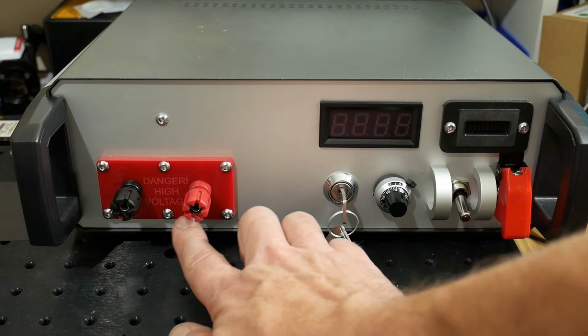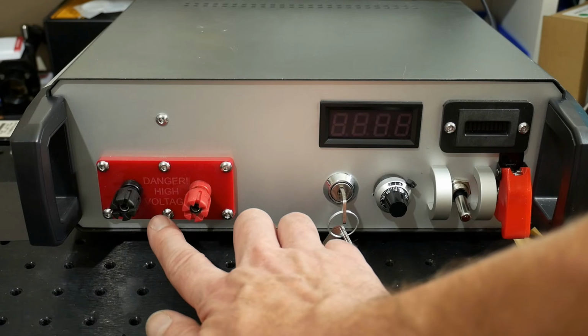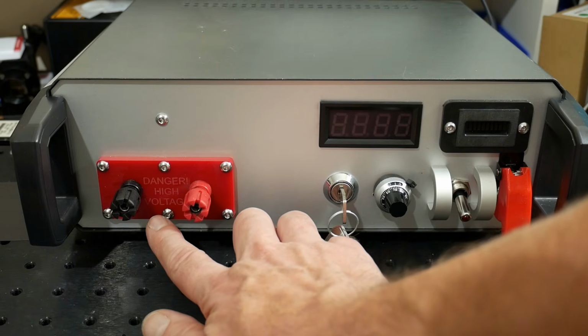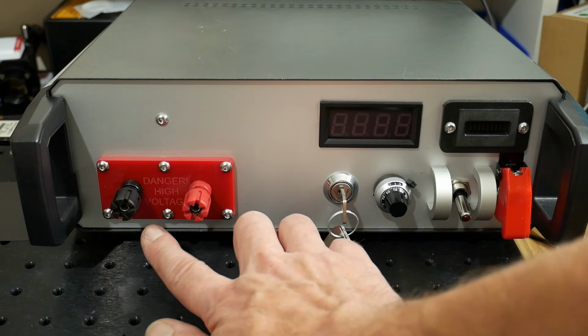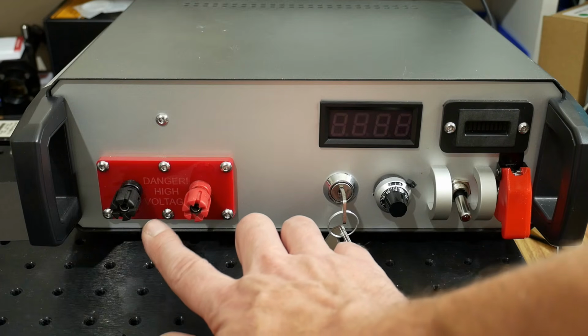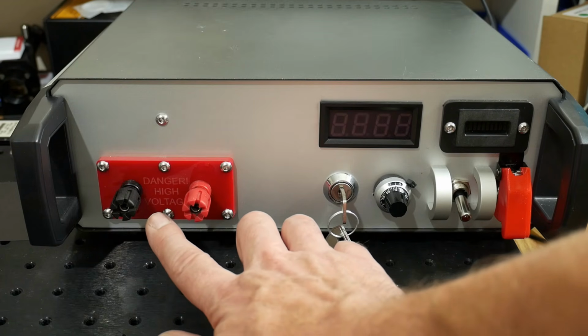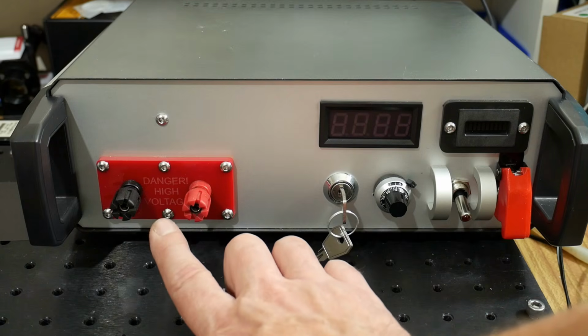On the front panel here I've got my high voltage out, internally connected to a 100 microfarad capacitor that can be charged to 1,500 volts. So you're looking at somewhere in the region of about 100 joules that can be discharged into a flash lamp, which is a very significant amount of energy.